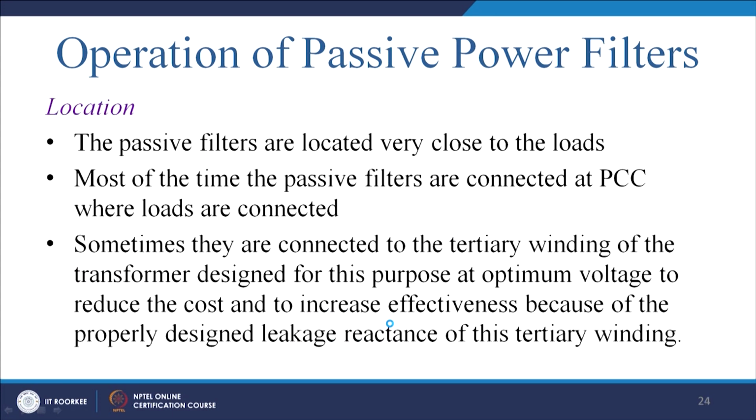And also this is something very important: the location of placing of the passive filter, where you will place it. Nowadays that is done by harmonic load flow study, and you have a saddle point of the particular harmonic. Because we have considered a one line system, but practically it is not so.